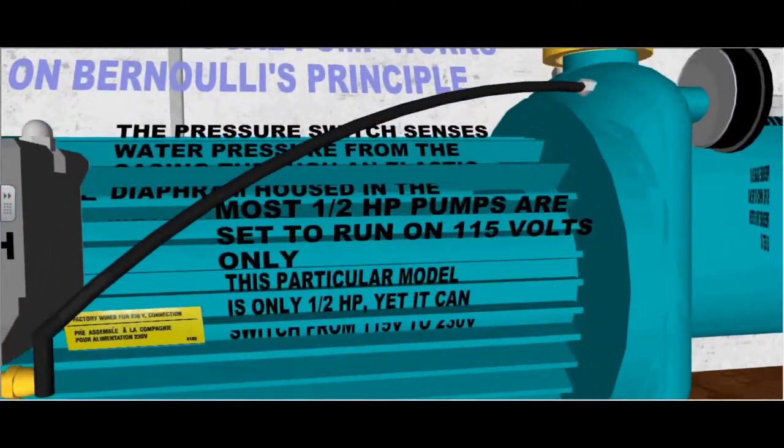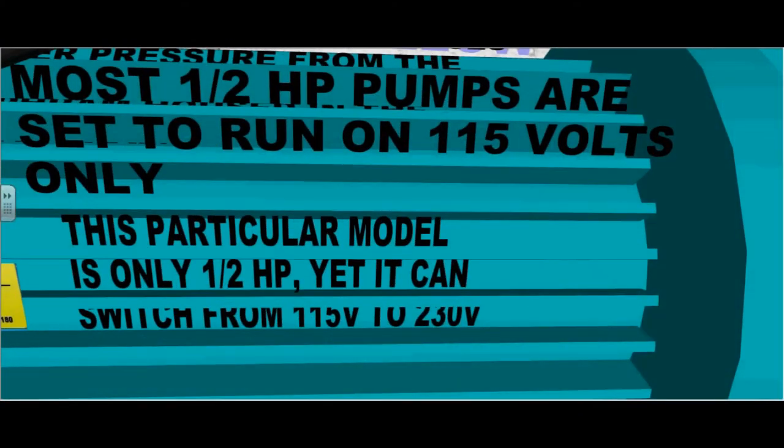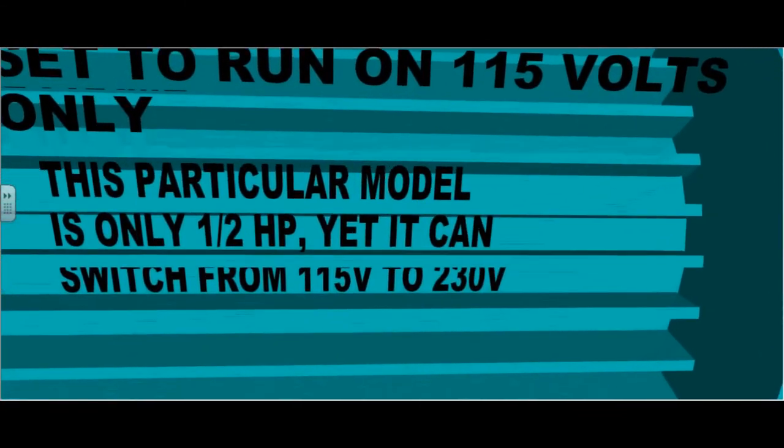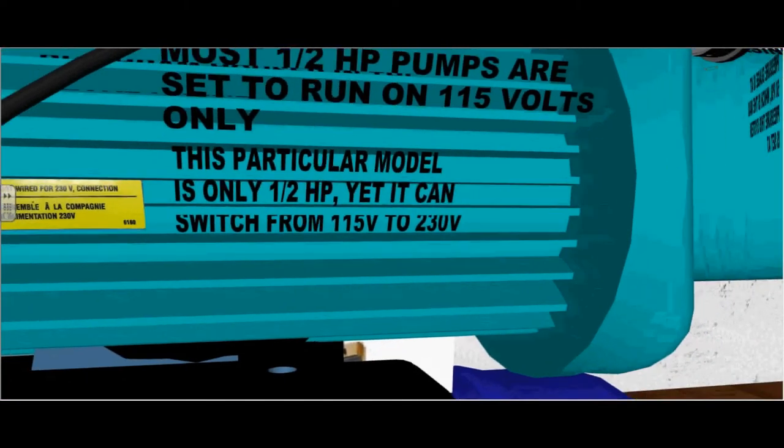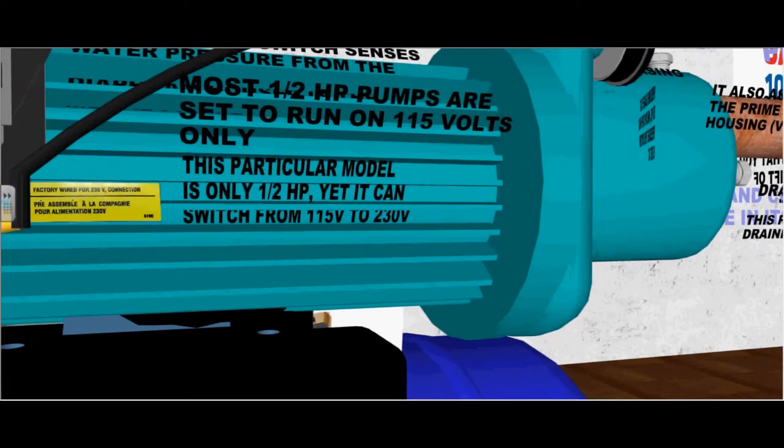This pic depicts the 13.2 gallon diaphragm tank and half horsepower jet pump in our shop. A centrifugal pump works on Bernoulli's principle. Most half horsepower pumps are set to run at 115 volts. This particular model is only a half horsepower, yet it can switch from 115 volts to 230 volts as illustrated on the factory wired stamp.